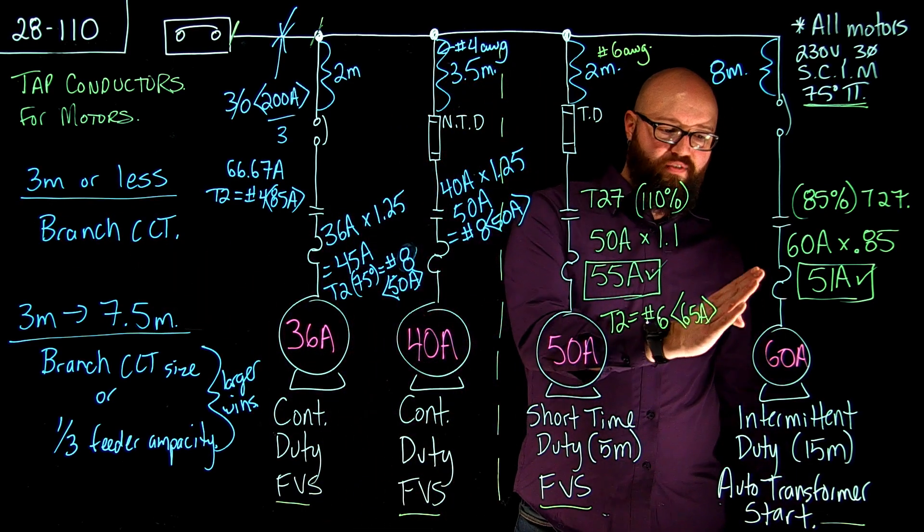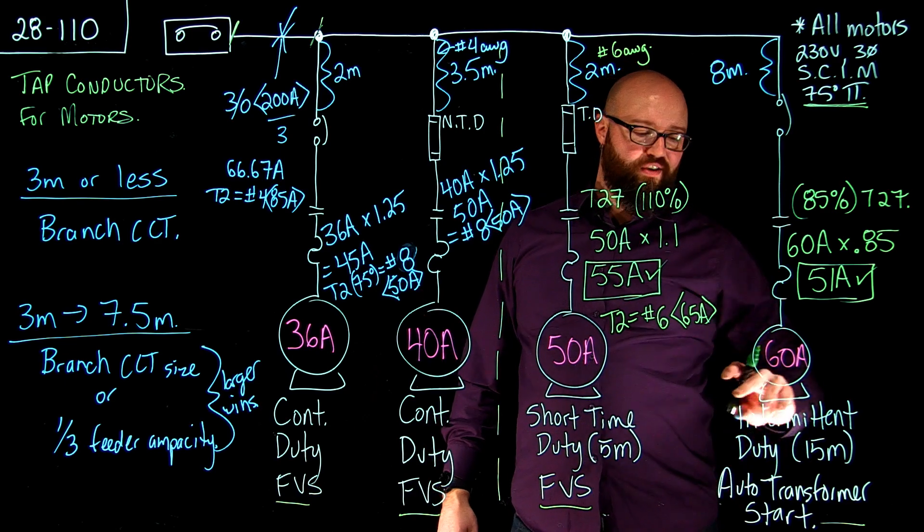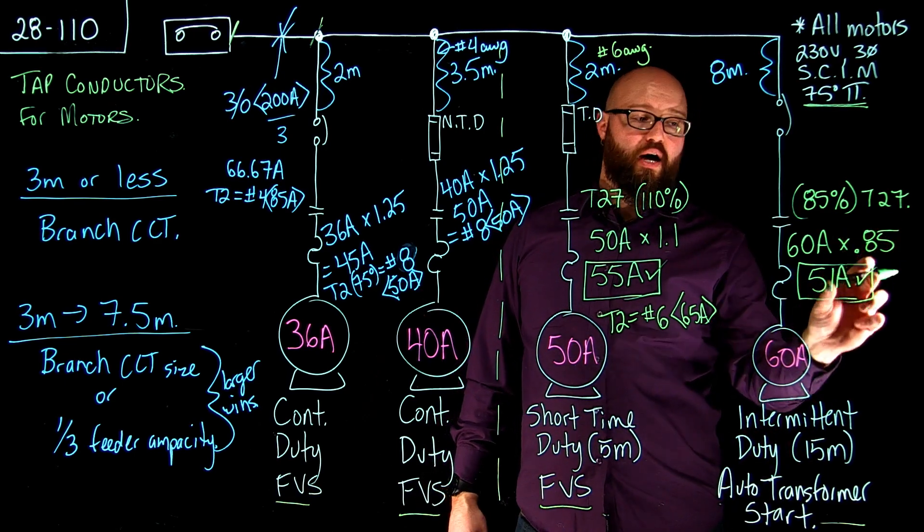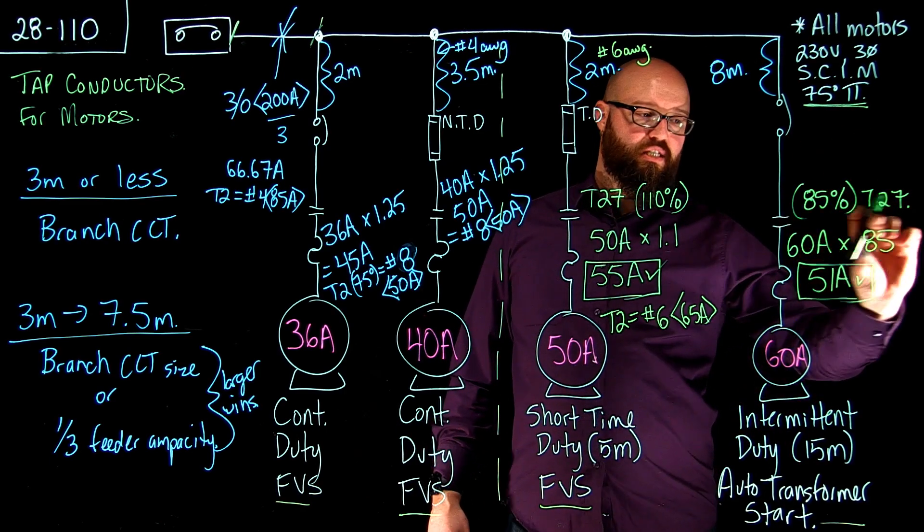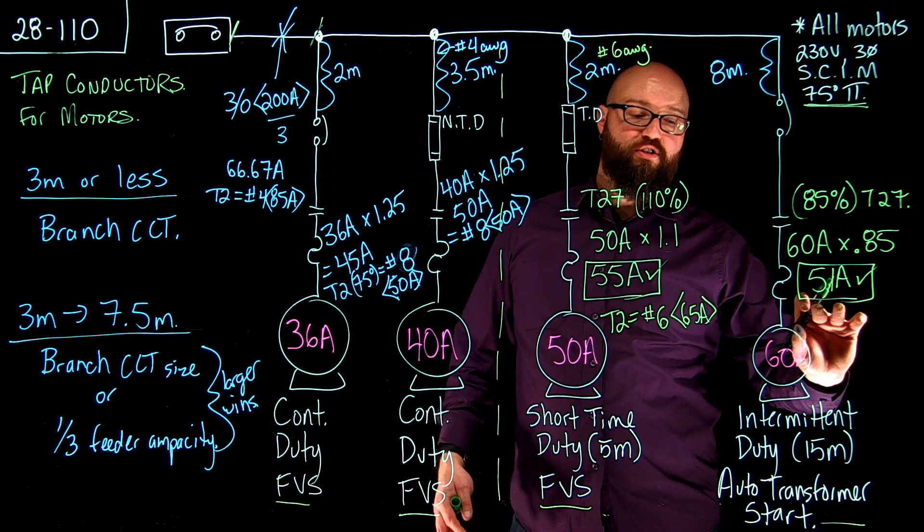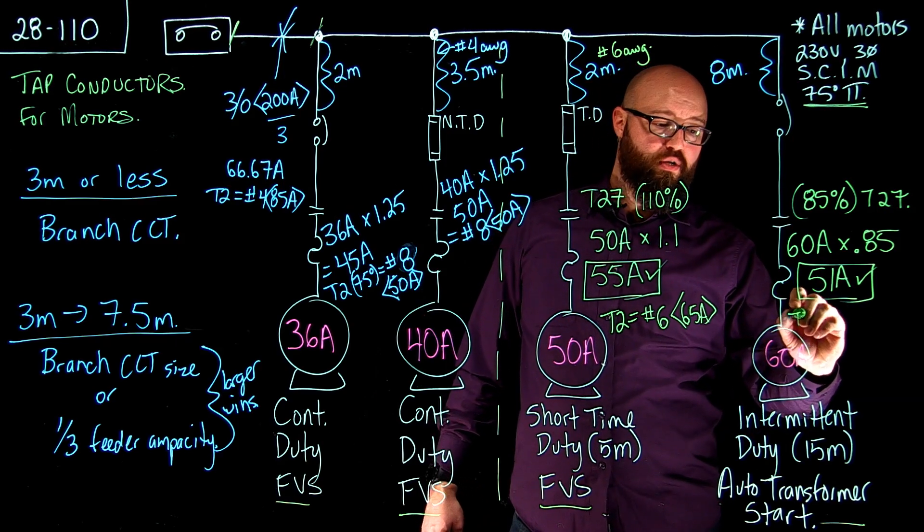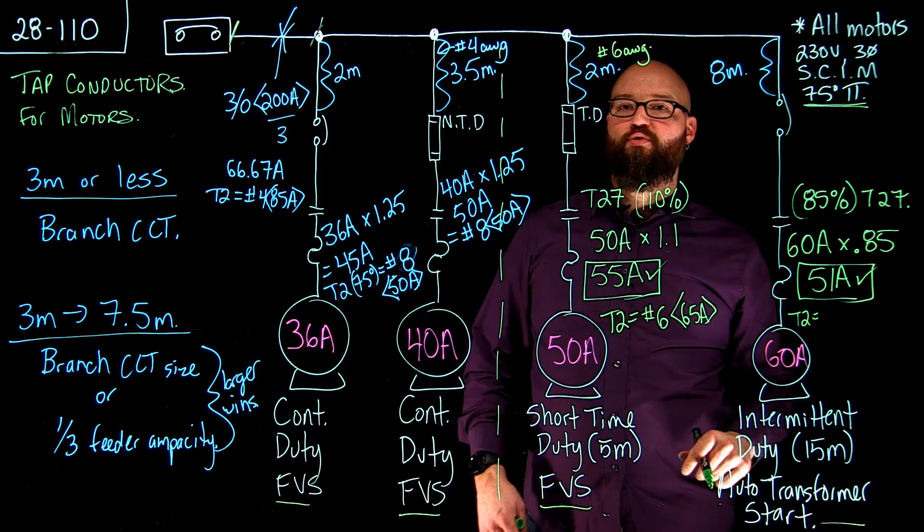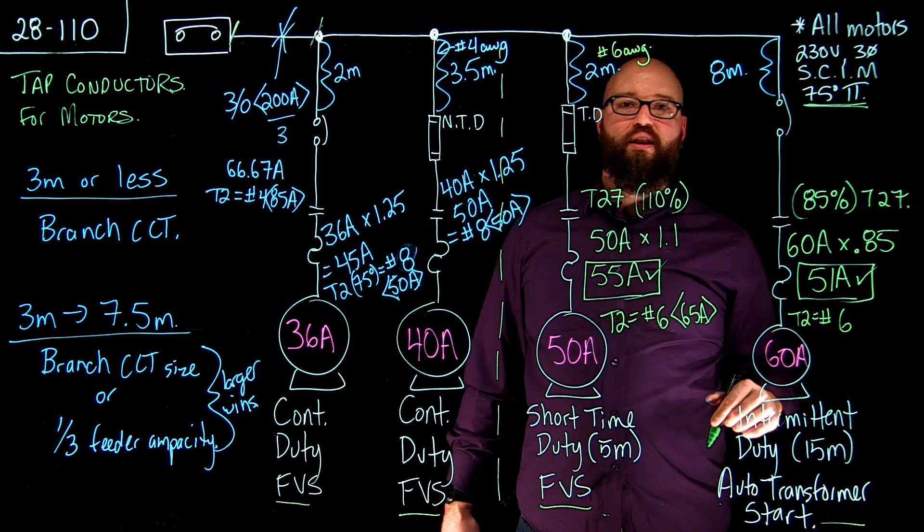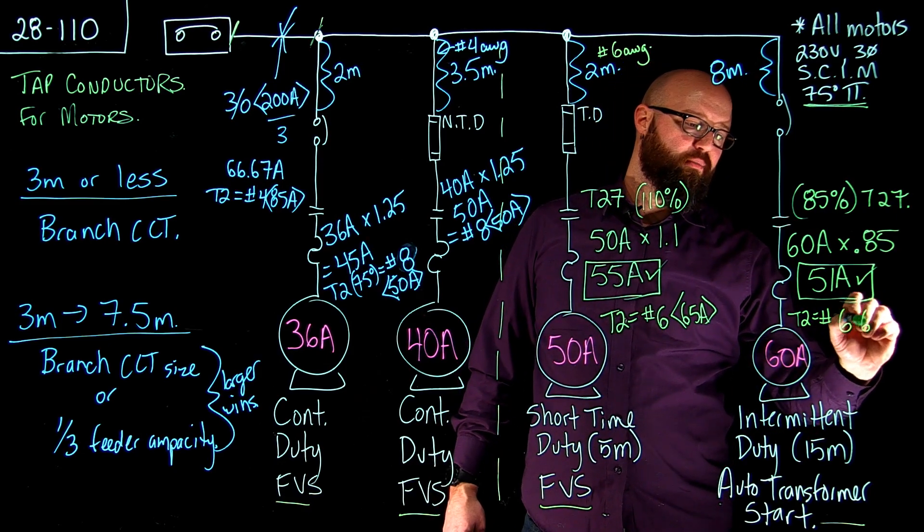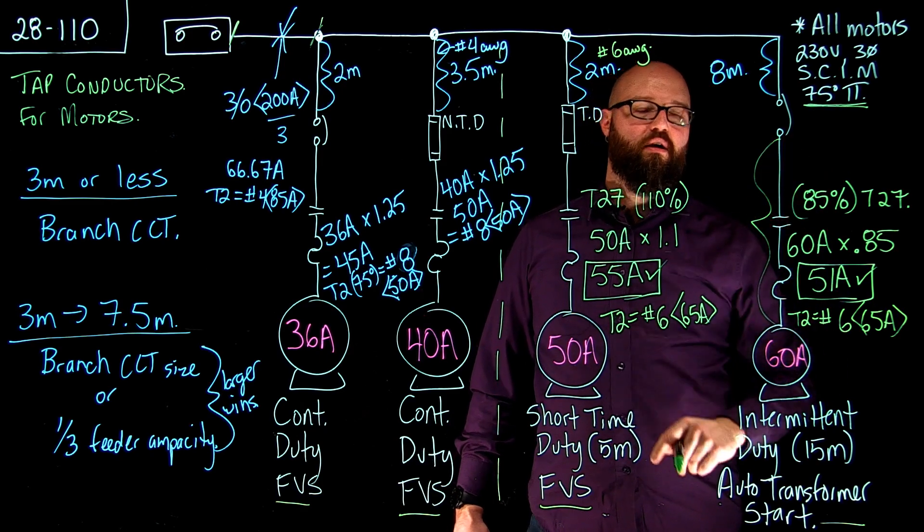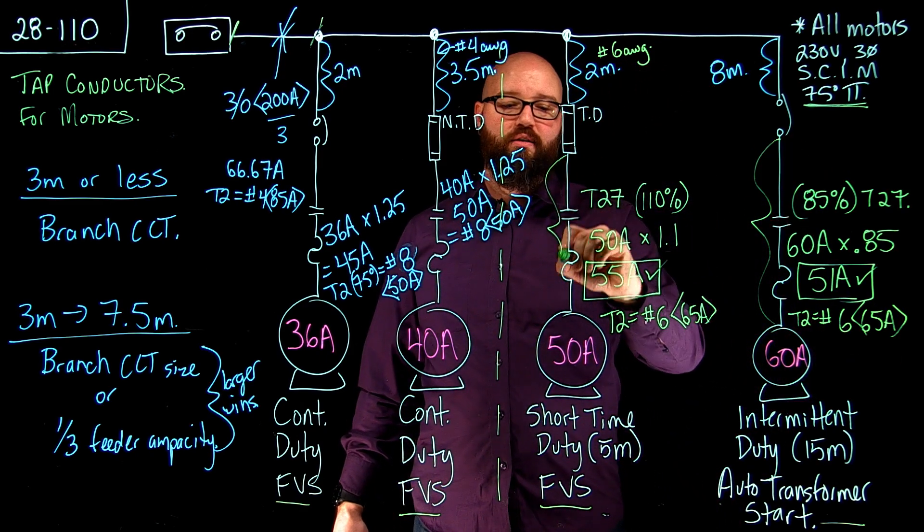Then we get to our last value here we have our 60 amp intermittent duty 15 minutes which gave us a multiplier from table 27 of 85%. 60 amps times 85% gave us 51 amp minimum capacity for our branch circuit. So we can go to table 2 and size our branch circuit which was or sorry which should be again a number 6 because we're just over that number 8 50 amps. So we're going to go with a number 6 65 amps. Again that's my branch circuit.